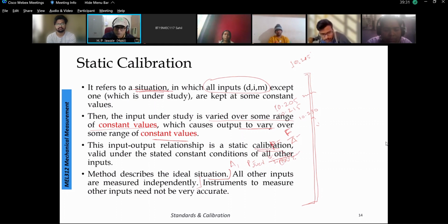Then we go on measuring the different entities which are responsible for torque. So for example, torque is nothing but a function of force as well as the distance at which the force is applied. Right. So we measure force accurately, we measure the distance accurately, and so on. So that is what it says. The method describes the ideal situation where all other inputs are measured independently. Instruments to measure other inputs need not be very accurate.